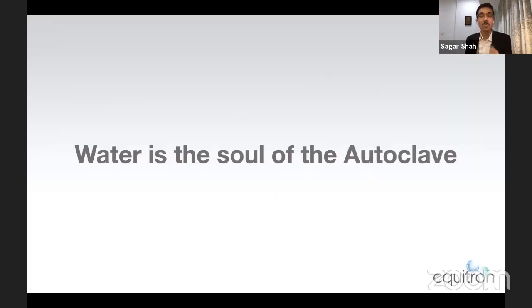So please note that tap water contains a variety of dissolved minerals and salts, and that's entirely dependent on your location and what is the water source. Is the water coming from a ground well? Is it coming from a lake, river, and so forth? The more minerals the water contains, the harder it is. And hard water is problematic. When hard water is boiled into pressurized steam, it leaves behind mineral deposits on the unit's chamber, heaters, valves, and even on your load. In fact, hard water is similar to layers of paint. These deposits will build up over time and will decrease the efficiency and functionality of the unit. So we recommend that you use only distilled water for your autoclaving needs.